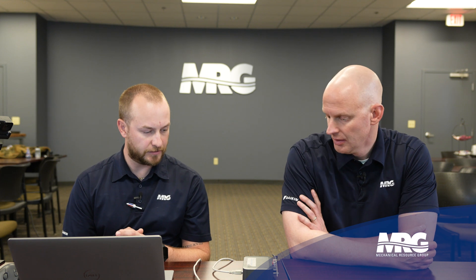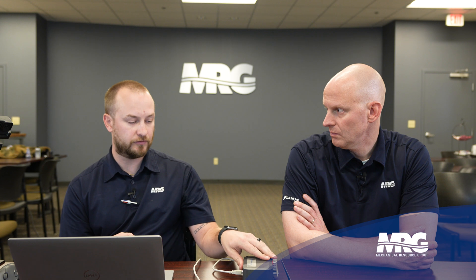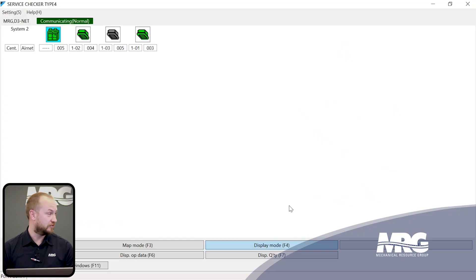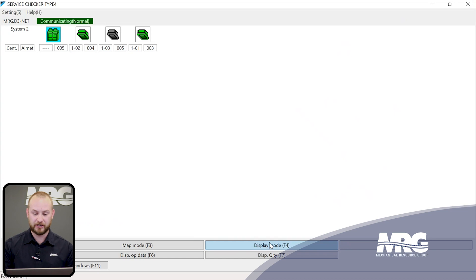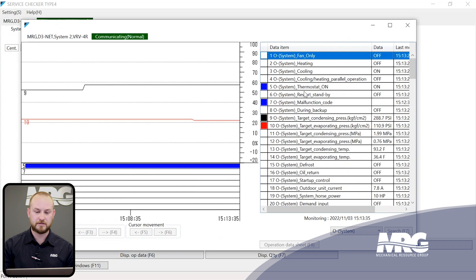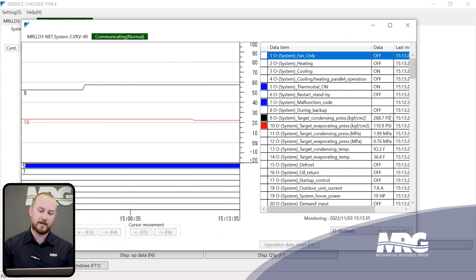We're hooked up — this is a Type 4 service checker, connected to our lab, landed on the F1/F2 output terminals of a VRV4 system. So we're able to sit here in the training room and look at the data. The first thing you want to do to view the data is come to Display Mode and click 'Display Operational Data,' which presents all of the data for the system you're looking at.